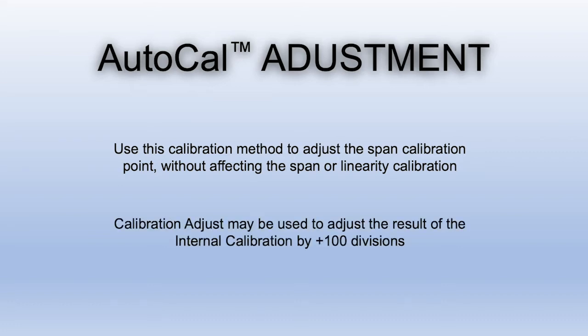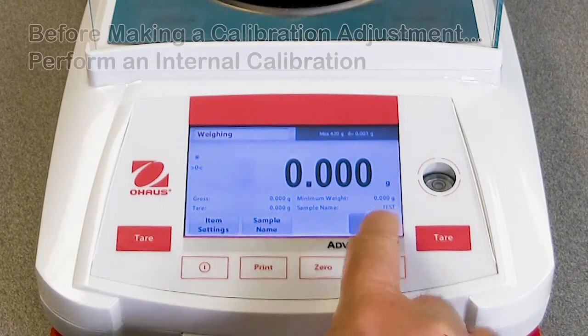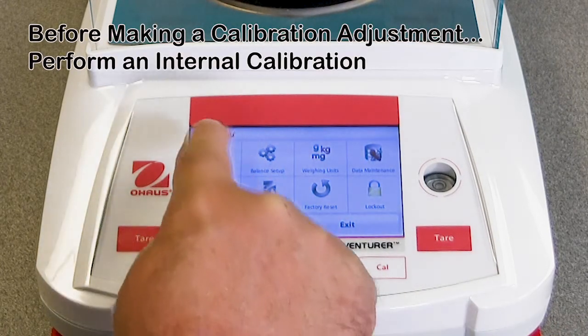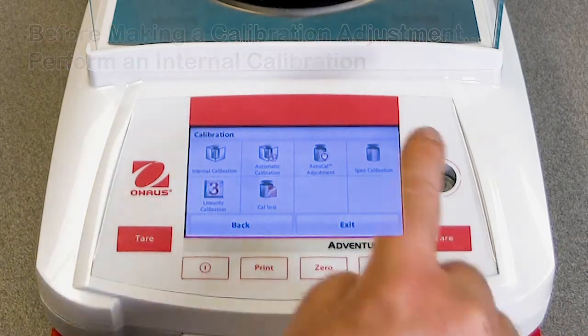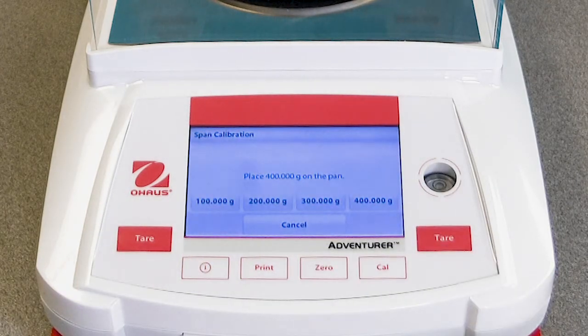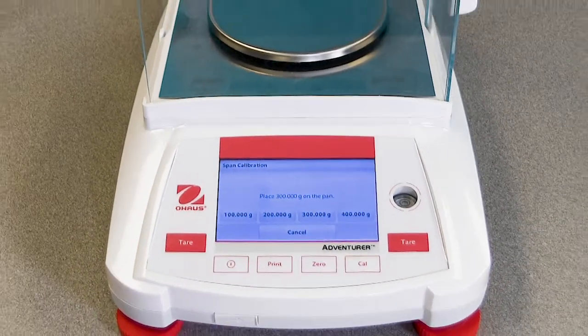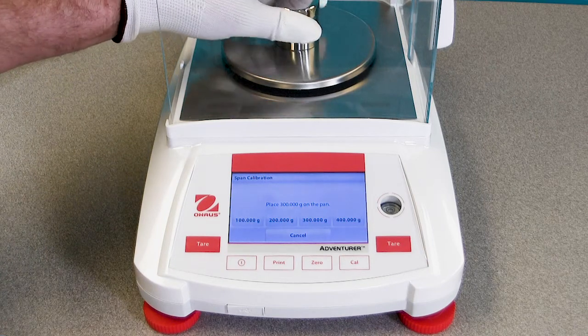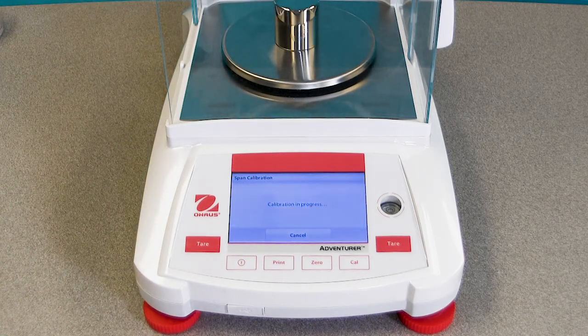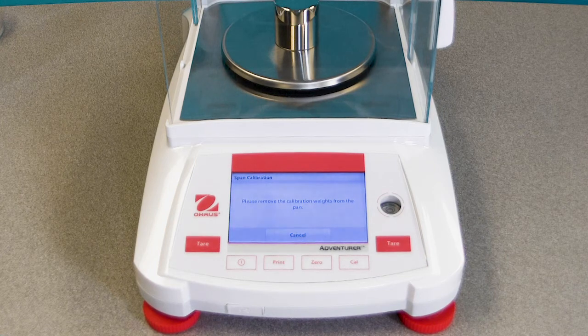Use the AutoCal adjustment calibration method to adjust the span calibration point without affecting the span or linearity calibration. Calibration adjustment may be used to adjust the result of the internal calibration by 100 divisions. Note: before making a calibration adjustment, perform an internal calibration. To verify whether an adjustment is needed, place a test mass equal to the span calibration value on the pan and note the difference in divisions between the nominal mass value and the actual balance reading.